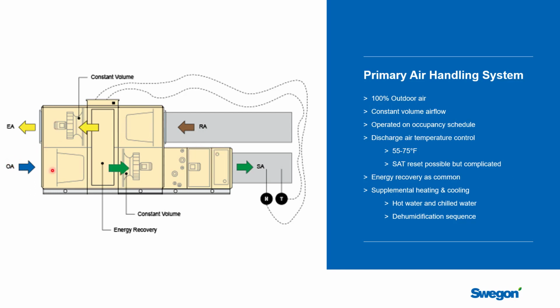It's very popular, but with an energy recovery device to recover as much energy as you can in both the summer and the winter, and so the return air is passing through one way, and the outdoor air is being brought into the unit and then heated and cooled and delivered to the space. The unit itself is going to have discharge air temperature control. Its purpose in life is to deliver air at a fixed temperature, so it's often somewhere between 55 and 75 degrees. Again, it depends on the design. There's no right or wrong answer.